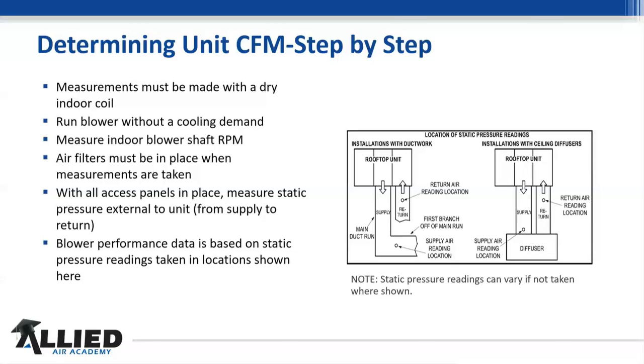So you can do it either way, but if you want the true CFM to start with, you want to do it with a dry coil. The reason being that if you run an air conditioner and you have multiple compressor circuits and one compressor is not running but another one is, it's going to throw your reading off. So when you get it with the dry coil, then you add that static pressure to it and you know what you've got. So you want to run it without a cooling demand. Sounds kind of weird, but yes, you want to run it without a cooling demand.